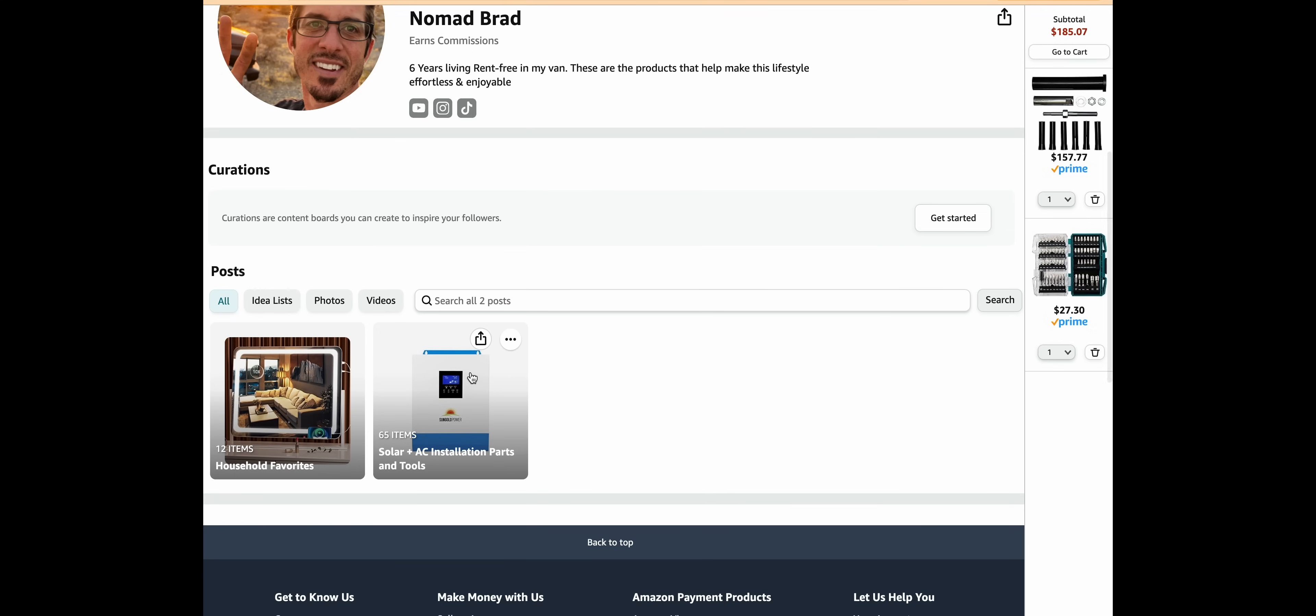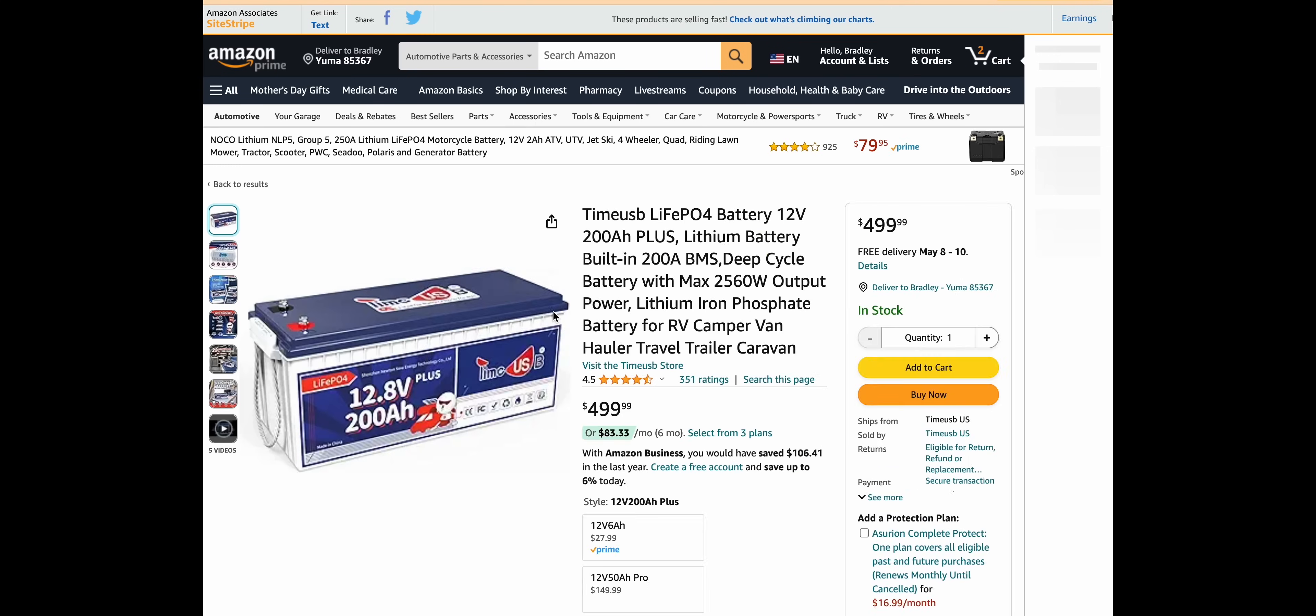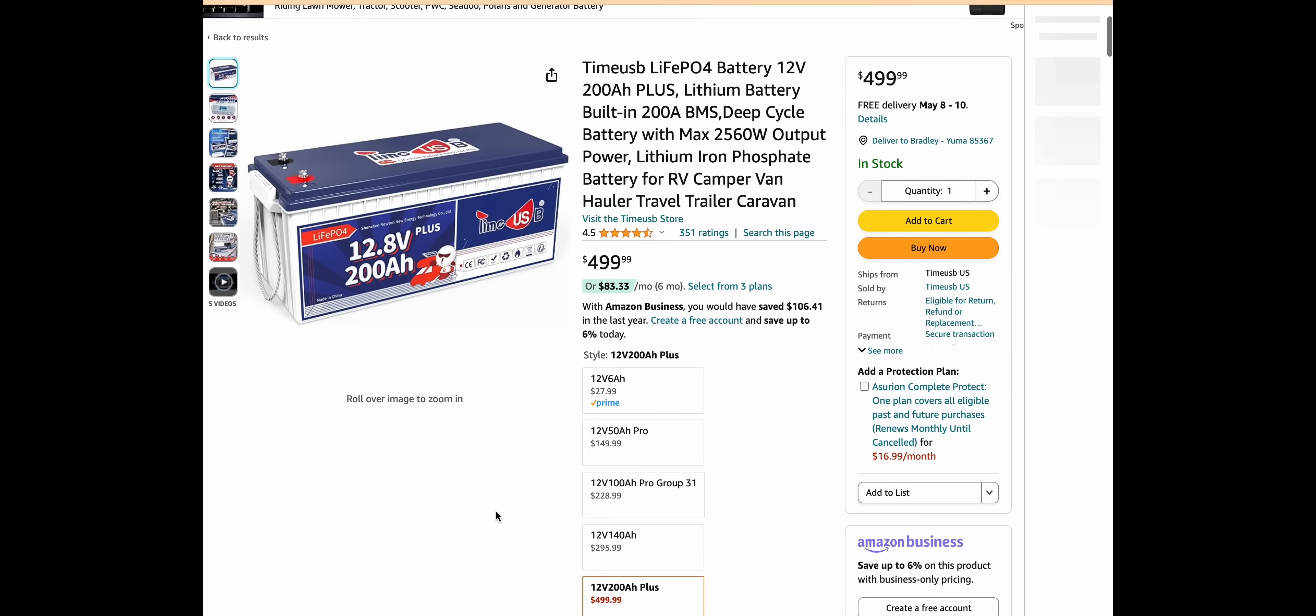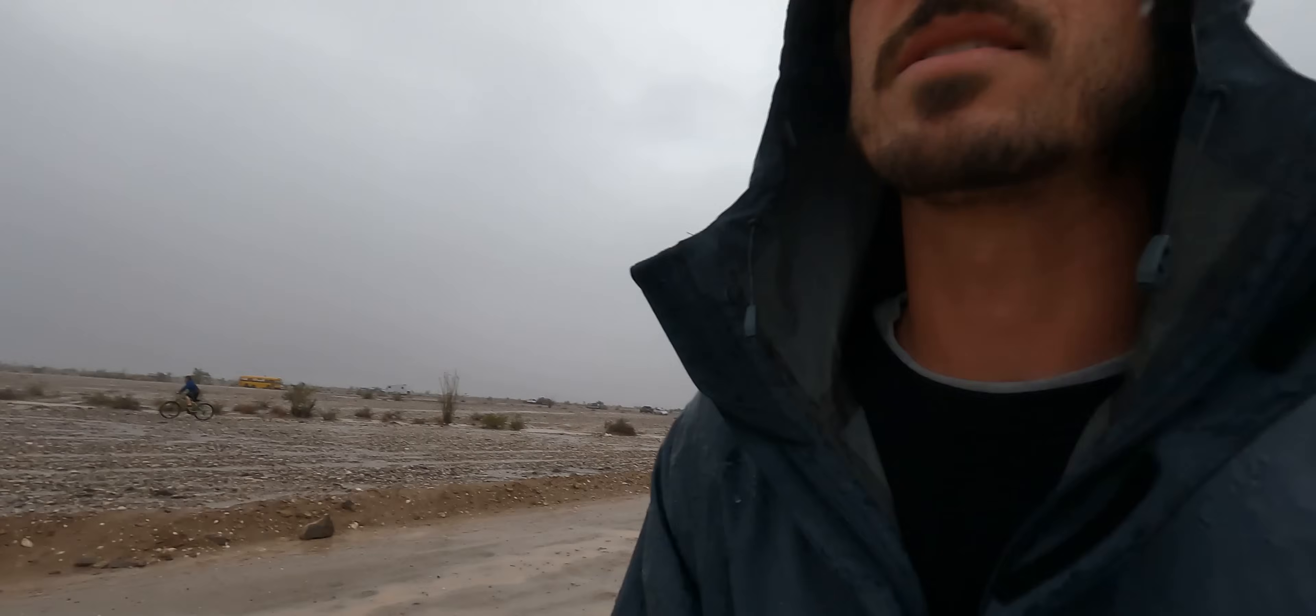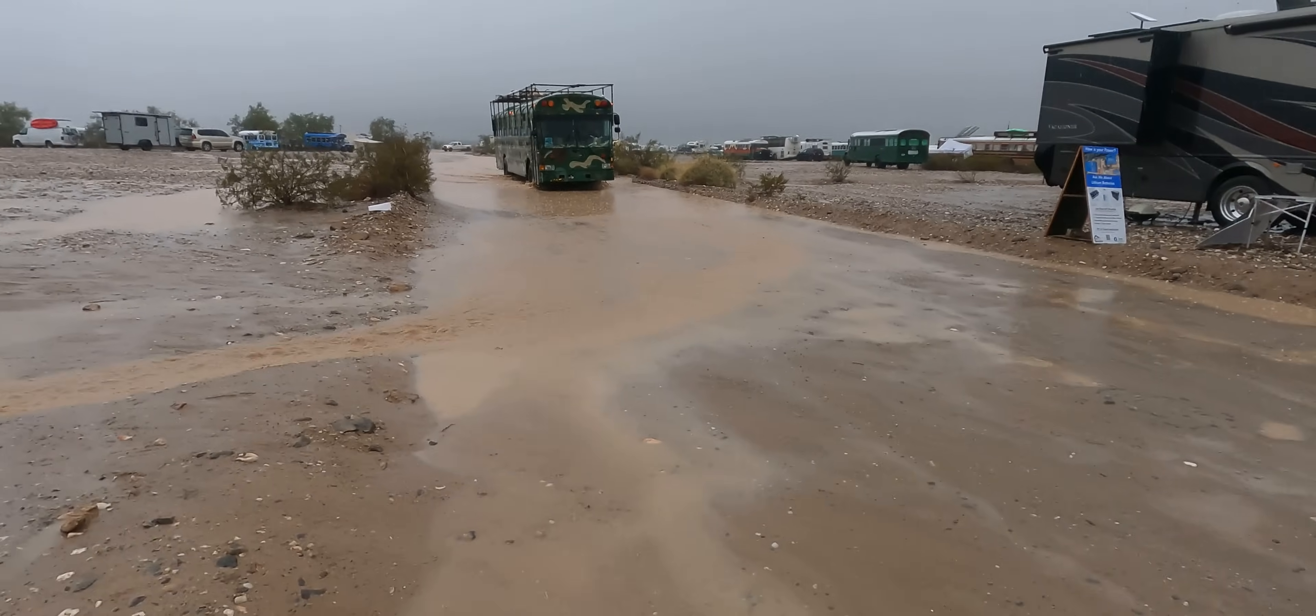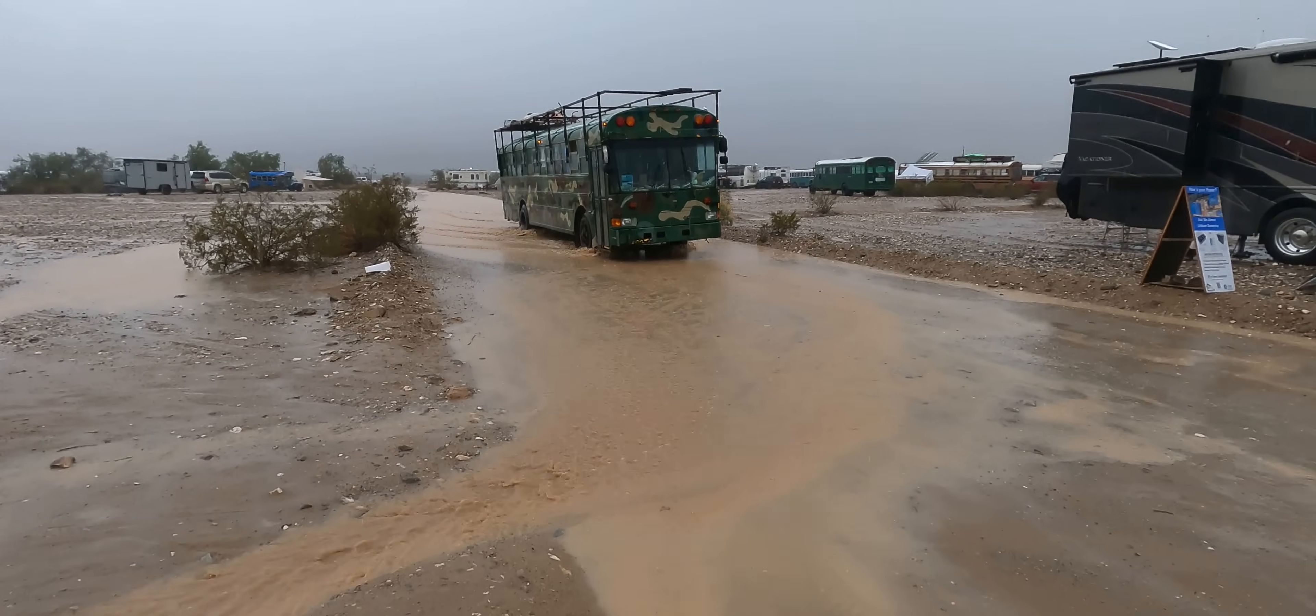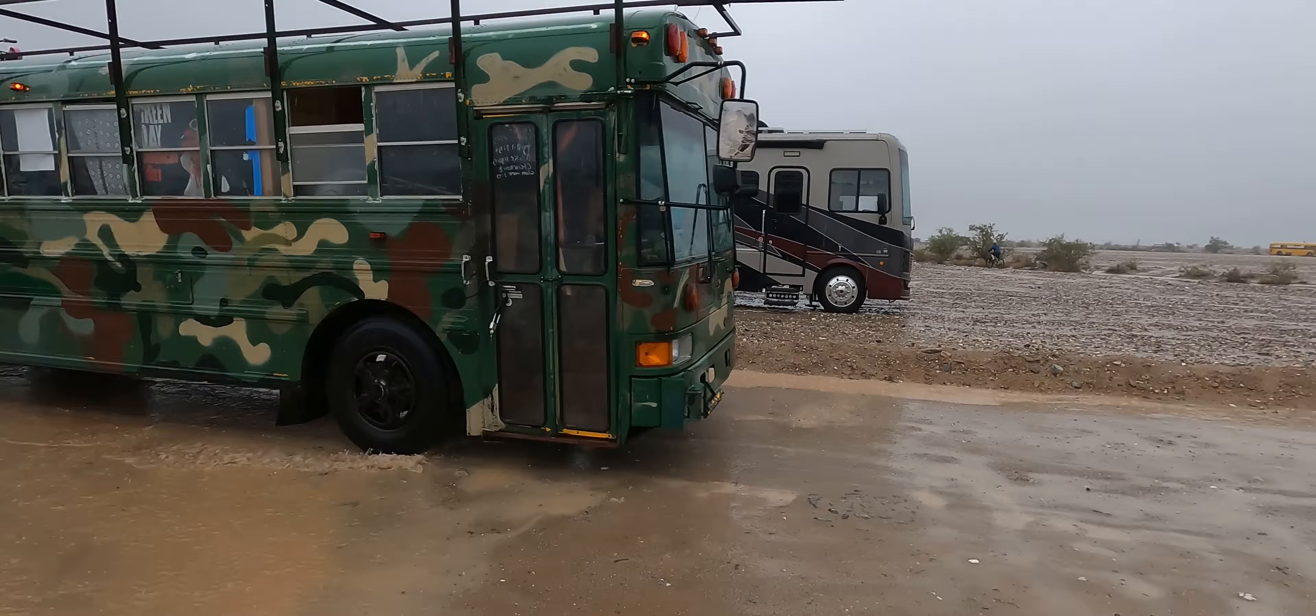Now the third step is to calculate your battery bank. I have two 200 amp hour, 12.8 volt lithium batteries, which store 2,560 watt hours each, totaling 5,120 watt hours for the entire bank. Lithium batteries can be safely discharged down to about 10% capacity, which means I have 4,608 watt hours available. Now keep in mind, the batteries are really just energy storage for the times when the sun is not out. Most of the day, you'll be running directly off solar power. And you should always have a little extra battery storage on hand.